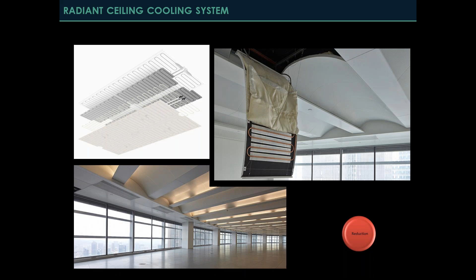Here's an image of an installed radiant ceiling system — at first glance you might not notice much difference. This is a project I worked on in China, a 2.2 million square foot office building in Guangzhou cooled entirely by radiant ceilings. I like to show this because people often incorrectly say you can't use radiant ceilings in hot, humid climates because they'll condense. Guangzhou is one of the hottest, most humid places on Earth, and they've never had a drop of condensation. So if properly designed, the system works anywhere in the world where you need cooling.